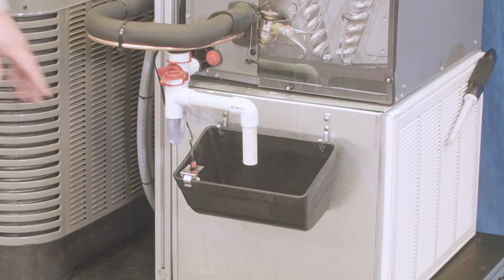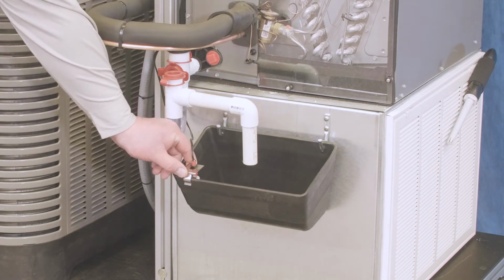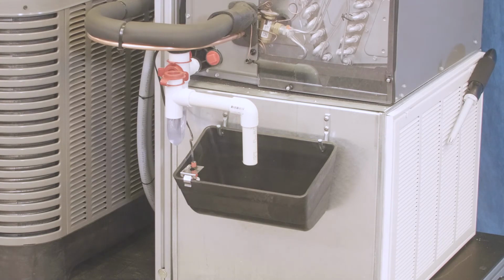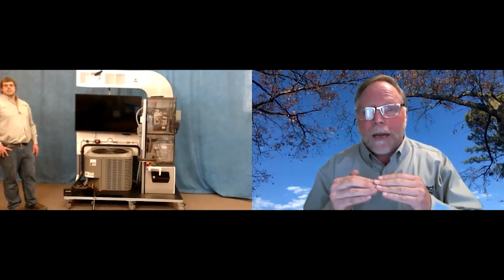Now, if it does spill out into an auxiliary drain pan, then we also have a safety switch in the auxiliary drain pan, which is in our drain pan here. And we've got that to simulate that. So we've got two safeties, one for the trap and one for the auxiliary drain pan. And with this system right here, we can show that as we run it. It depends on what condition your unit's in. But if I get this unit out in my lab and I get it really nice, I open the doors, it's summertime, and I let some heat and humidity into that lab, then this indoor coil begins to produce a lot of condensation. And when it's first started up, that trap is dry. And you'll see the water start to build up inside the drain pan of the evaporator coil because it's plexiglass, and you can see that happening.